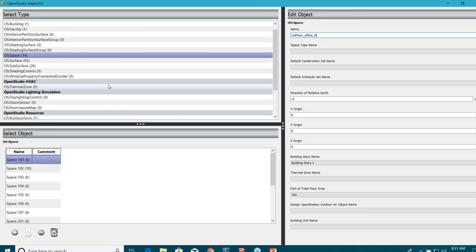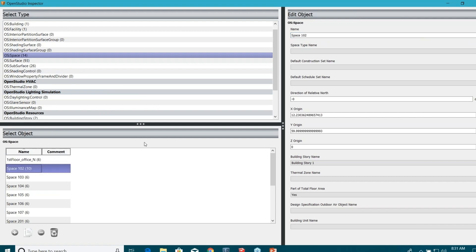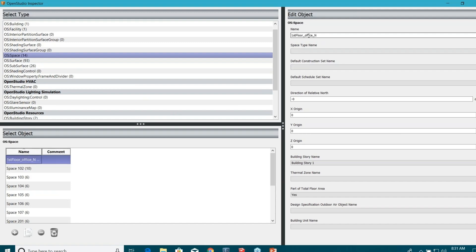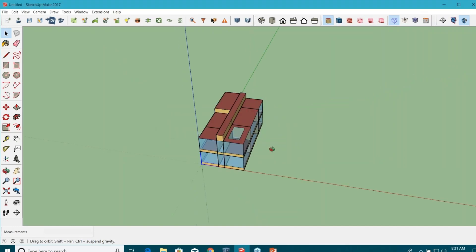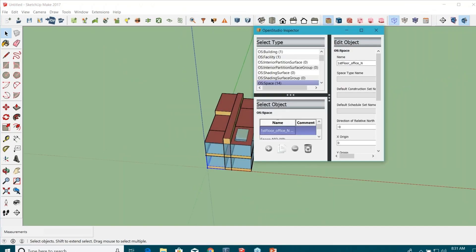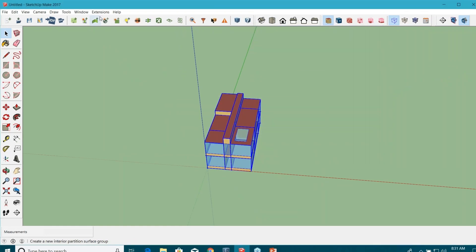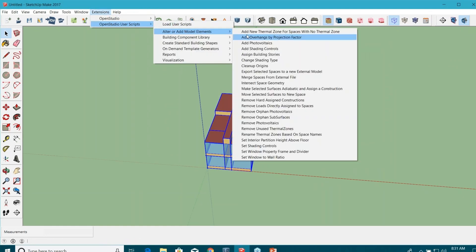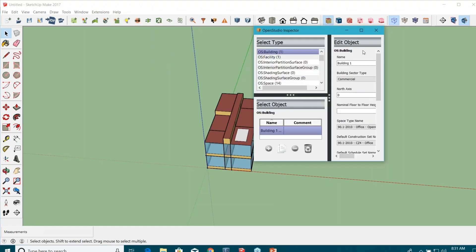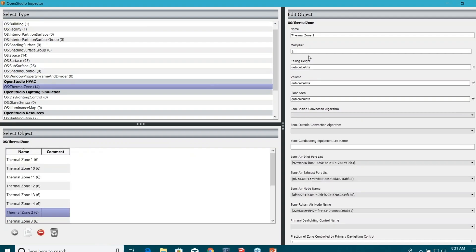Please, when you're working on this tool or even on eQuest or any other energy tool, it's a very good practice to rename your important components the way you want. That's why I like to do 'first floor underscore office underscore north' — so I know which floor and which space I'm working on. Now I'm going to select each and every space in my model and use another script: 'add new thermal zones for spaces with no thermal zone.' Click on it. And now if you go back to the inspector tool, you can see 14 thermal zones here.